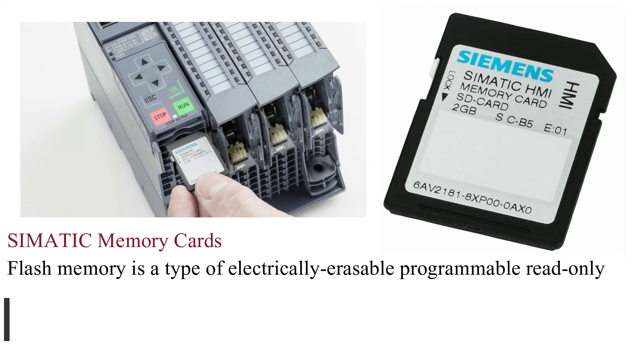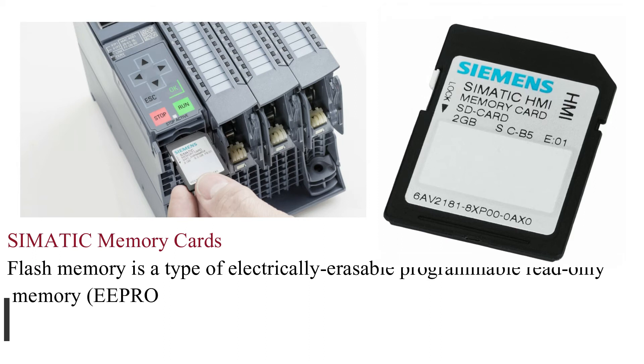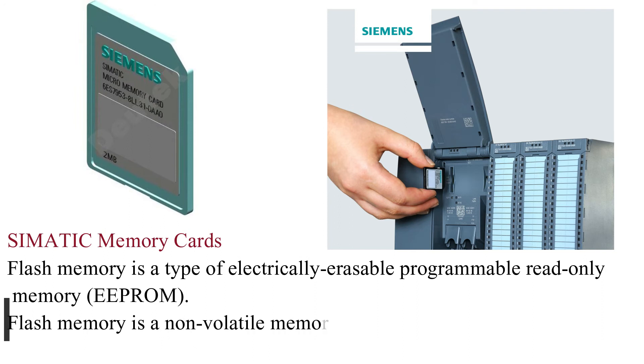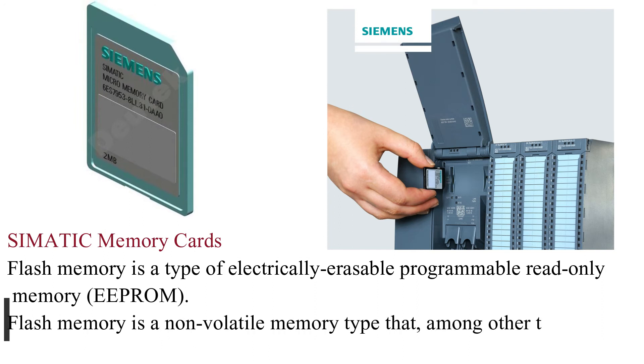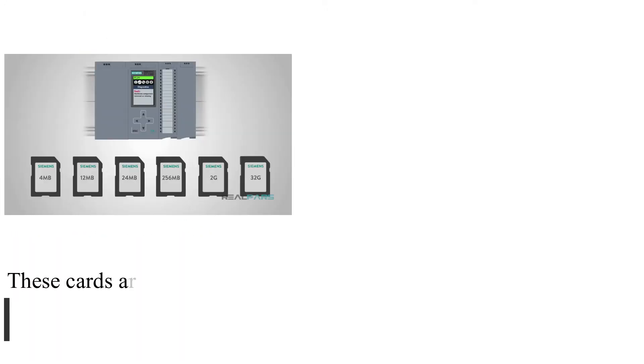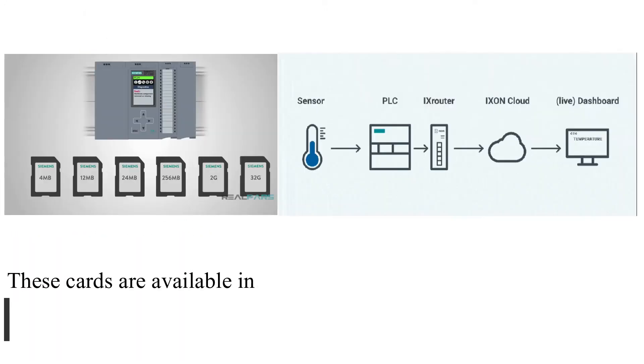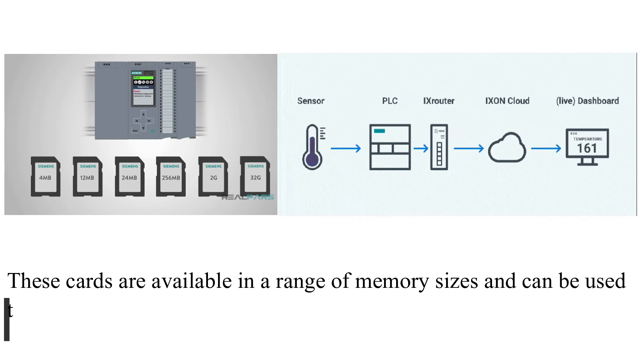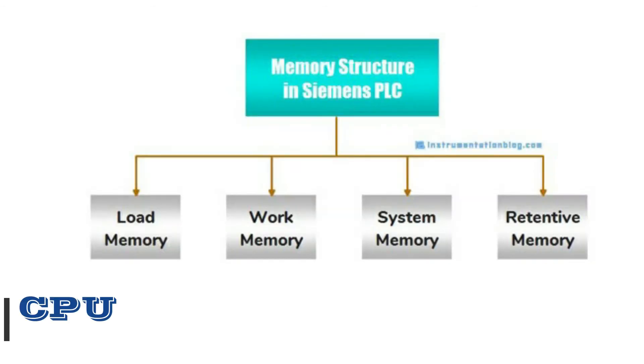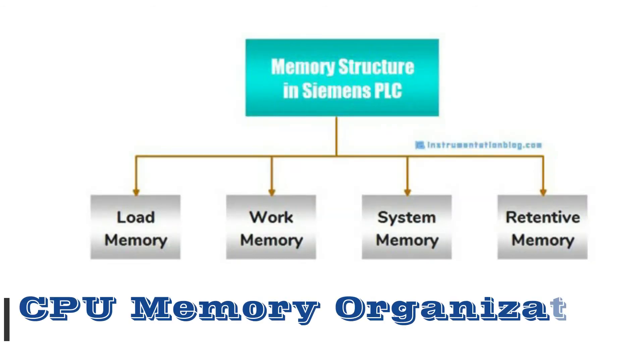Flash Memory and SIMATIC Memory Cards: Flash Memory is a type of electrically erasable programmable read-only memory. Flash Memory is a non-volatile memory type that, among other things, is used for SIMATIC memory cards. These cards are available in a range of memory sizes and can be used to store or transfer a PLC user program and associated data.